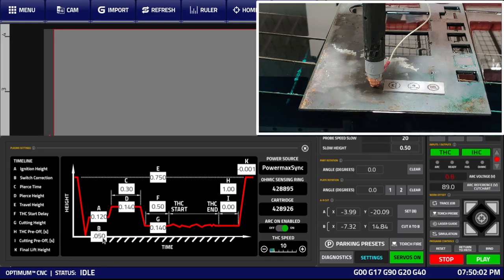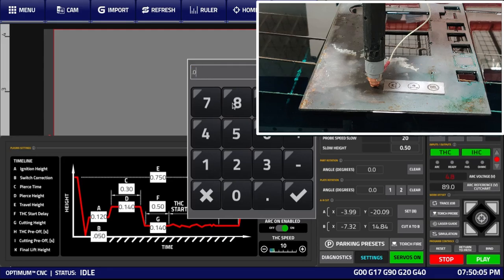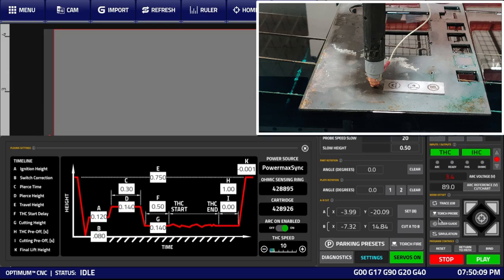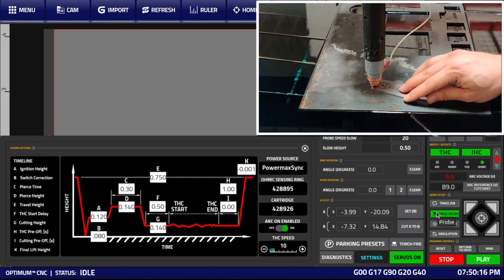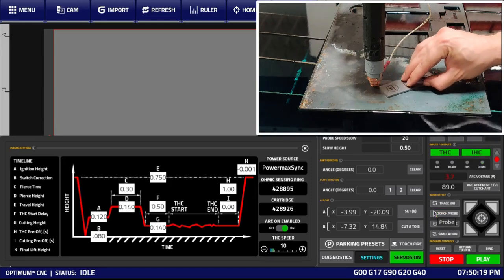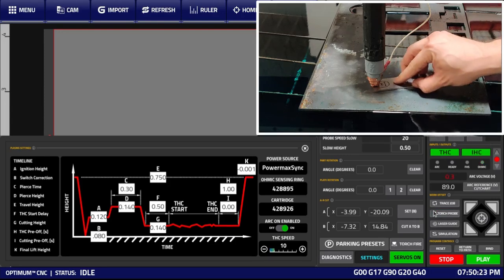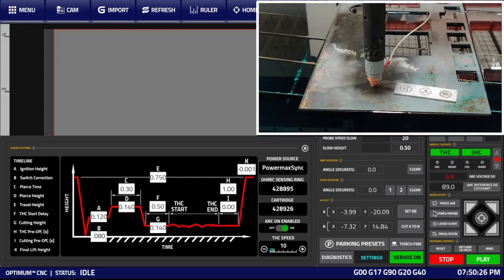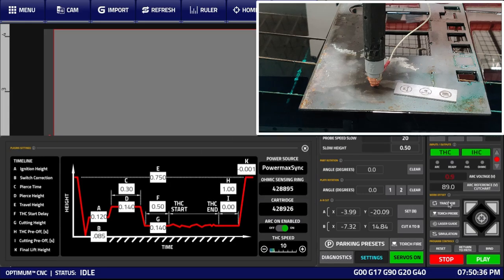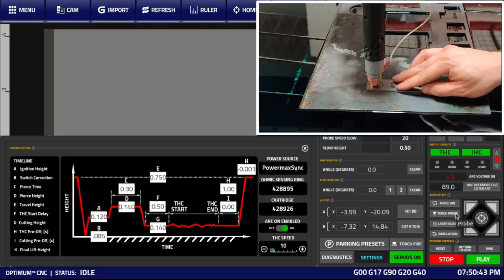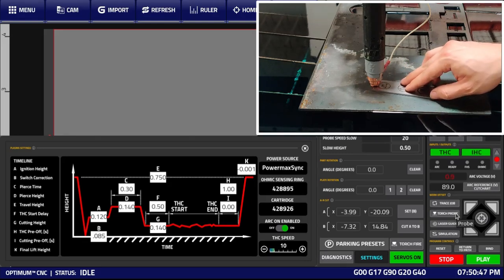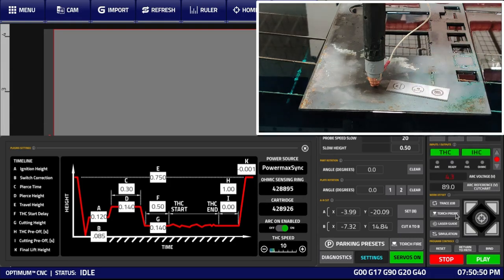So we're going to go and adjust this value to be a little higher by about 30 thou to 0.08. Run the torch probe procedure again. And once we try and fit this plate under the torch, we can slide it under, but there is some resistance. In this case, it's usually better to adjust the switch correction to be a little bit higher. Typically a few thousandths of an inch higher is better than a few thousandths of an inch lower, so we're going to go and adjust it to 0.085. Run the torch probe again. Slide the reference plate under the torch, and here we have a plate that slides under the torch easily, but there's no real air gap, so we now have our switch correction.